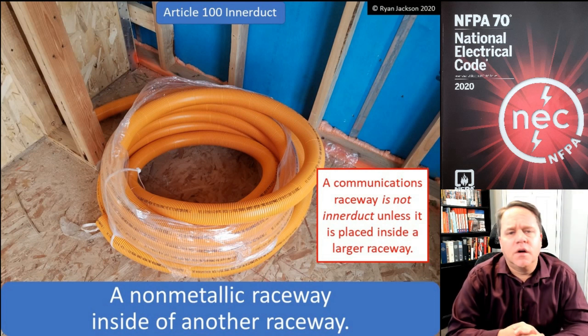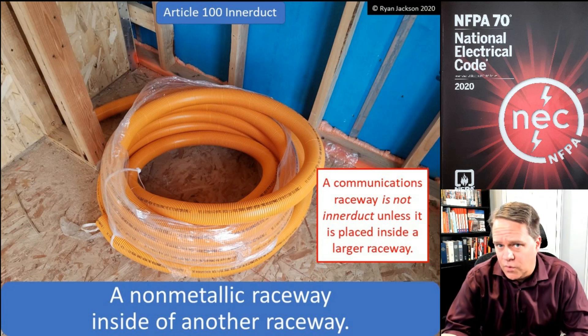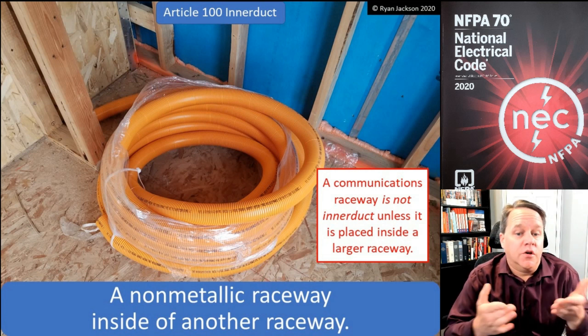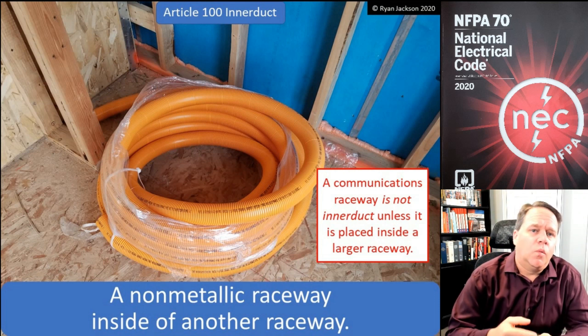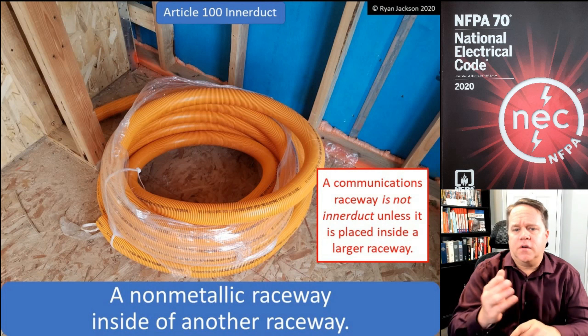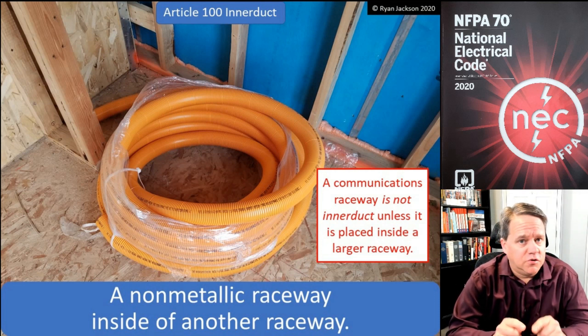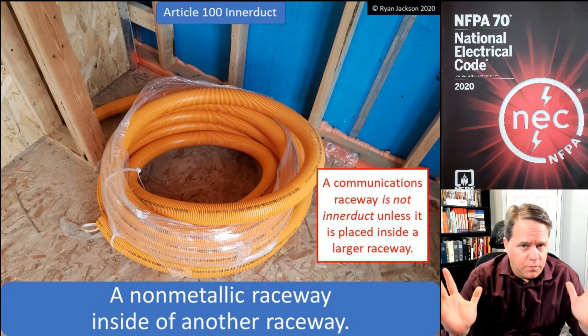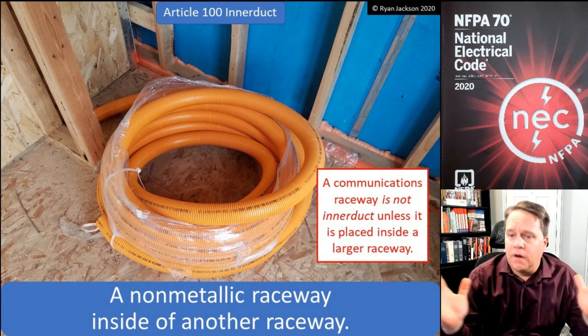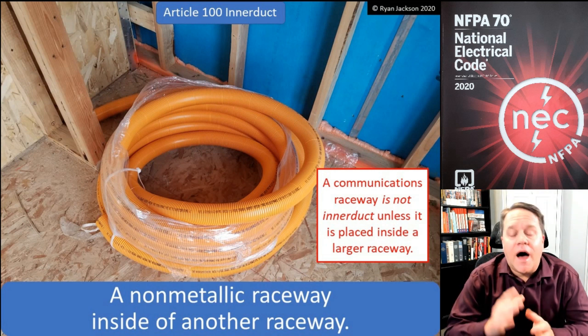Innerduct is a non-metallic raceway inside of another raceway. Now, could you go to the parts store and buy a non-metallic raceway that's inside of another raceway? Sure. But what a lot of people think is innerduct is they buy a roll of electrical non-metallic tubing that's orange — we usually call that a communications raceway — and you pull your communications cables through it. Well, that's not innerduct.